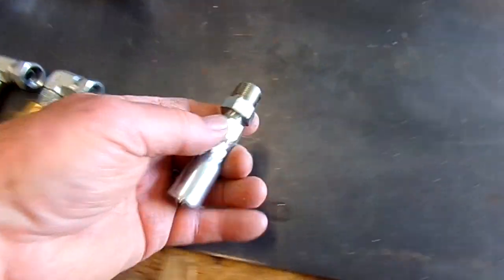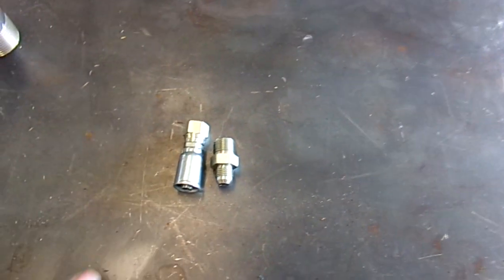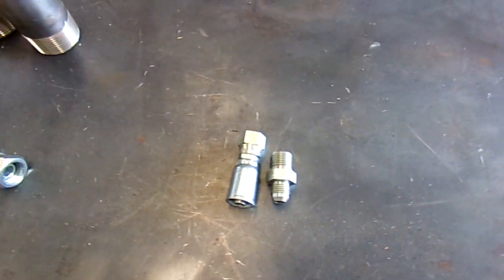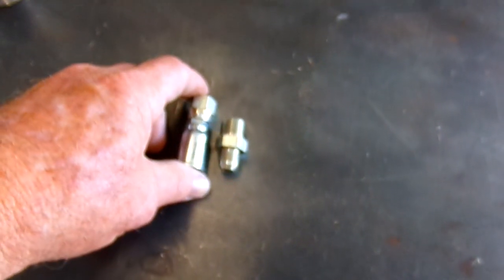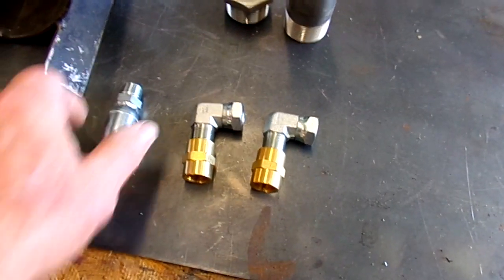We used to use braided Teflon hoses, but I'm getting away from them except for low PSI applications or chemical feed. When it has to do with the high pressure system, we've gotten away from these because the 3/8 Teflon hoses, due to the larger Teflon surface area, are only 2,200 PSI. The quarter hoses are 3,000 PSI, but because you've expanded the size with the same thickness of Teflon, you've weakened it. So we're only using high pressure, robust, steel mesh reinforced hoses on our units.